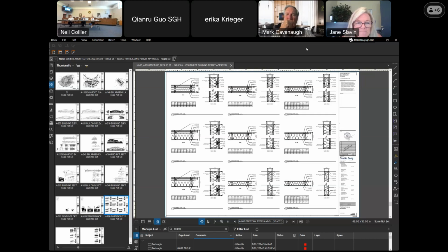One of our typical ways of dealing with a distance longer than standard is to add extensions of the sprinkler system that give firefighters connection points on the far side of the building—2.5-inch and 1.5-inch hose connections, like you'd see in a stairway enclosure of a medium-sized or tall building. So instead of dragging a hose around the outside, they can hook up on either end of a pipe that's already in place. That's what we intend to present to the responding fire department as we get into the permitting process. The code officials have seen the initial issue-for-permit set, but the back-and-forth, explanation, and haggling of the permitting process is only now beginning.